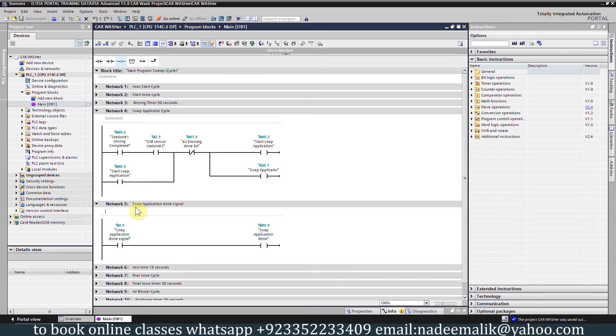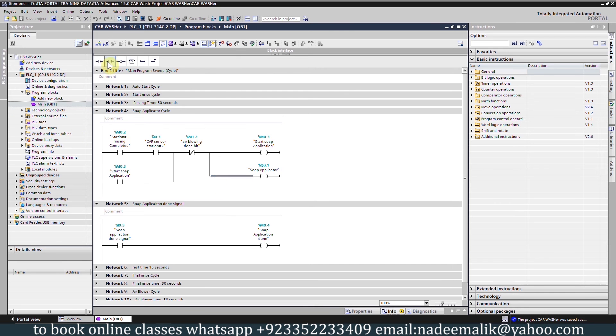In network number 5 we have the soap application done signal. When the soap applicator moves around the car one time it will send a signal to PLC input I0.5 to indicate that soap application is done. This turns on bit M0.4, the soap application done bit. We insert a normally-closed contact of this bit to turn off the soap applicator output.